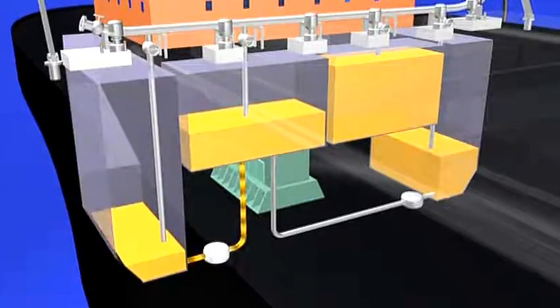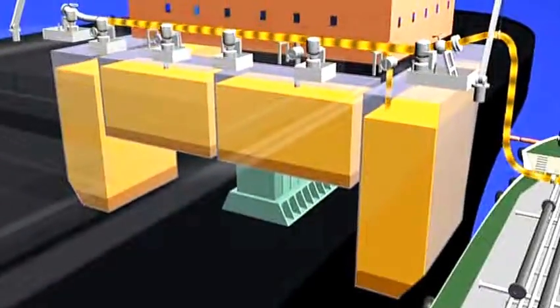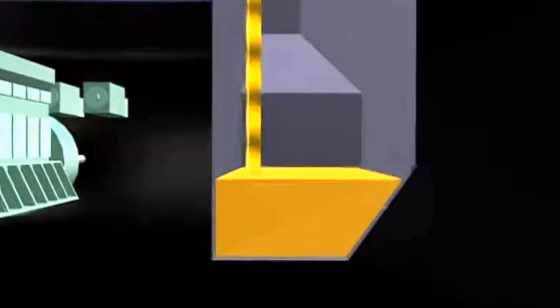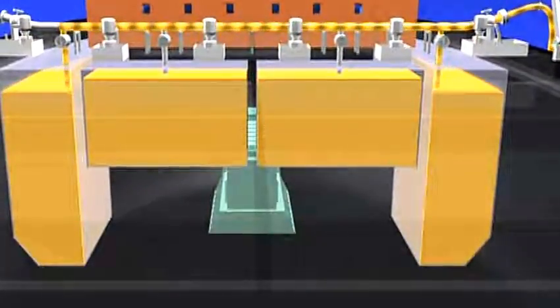Depending on circumstances, you may have to consider tank-to-tank transfer operation of residual oils. If mixing of bunker fuel with residual oil cannot be avoided due to capacity availability, try to minimize the ratio of residual oil. In general, plan to avoid mixing fuel and residual oil. To prevent tank overflow, always make sure that the maximum quantity of bunker fuel received by each tank does not exceed its capacity limit.